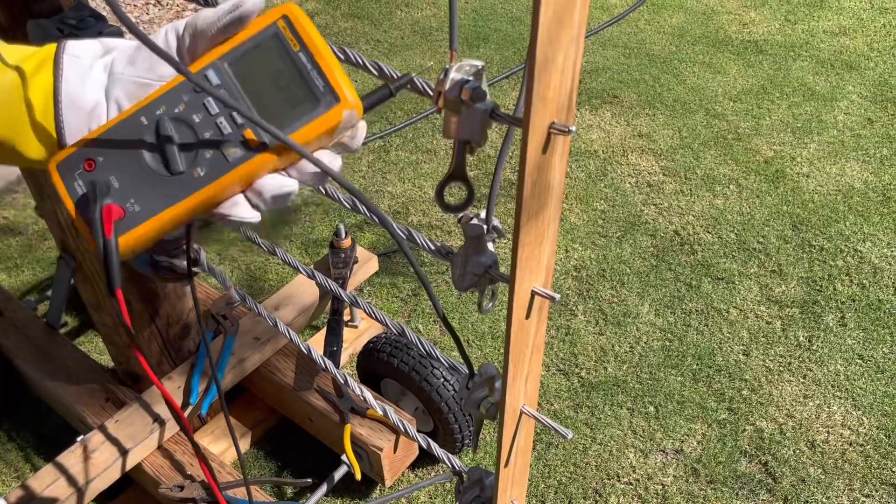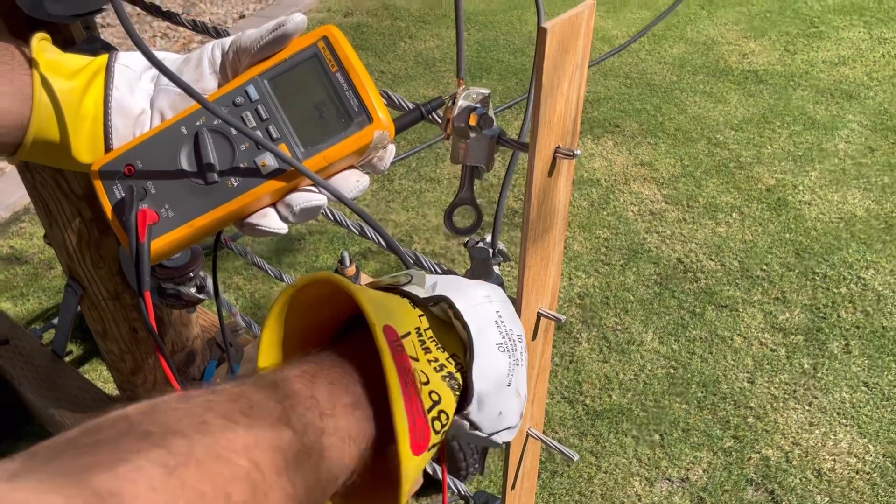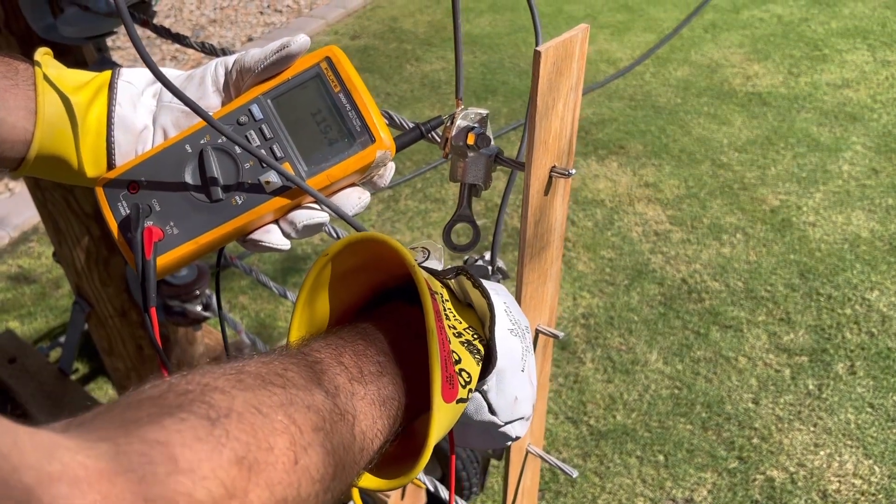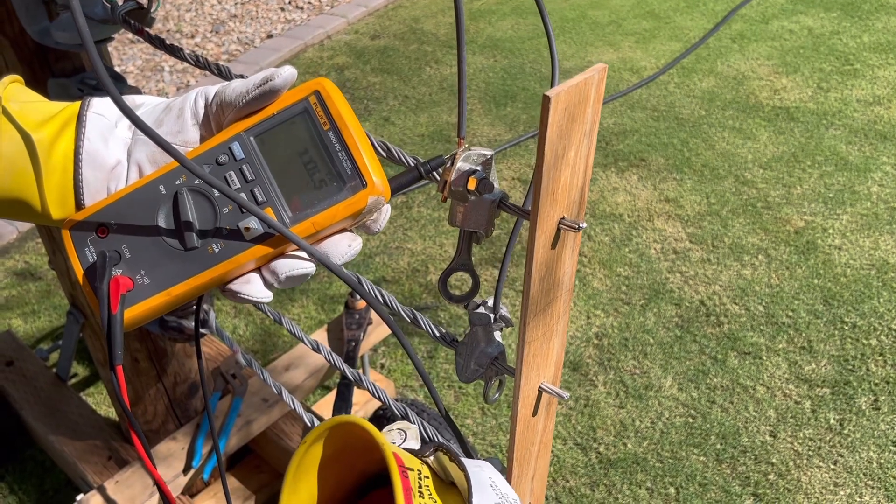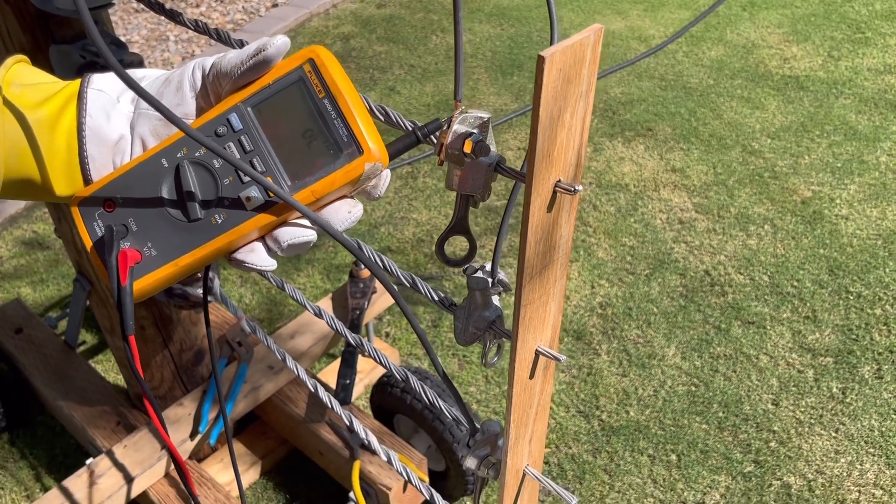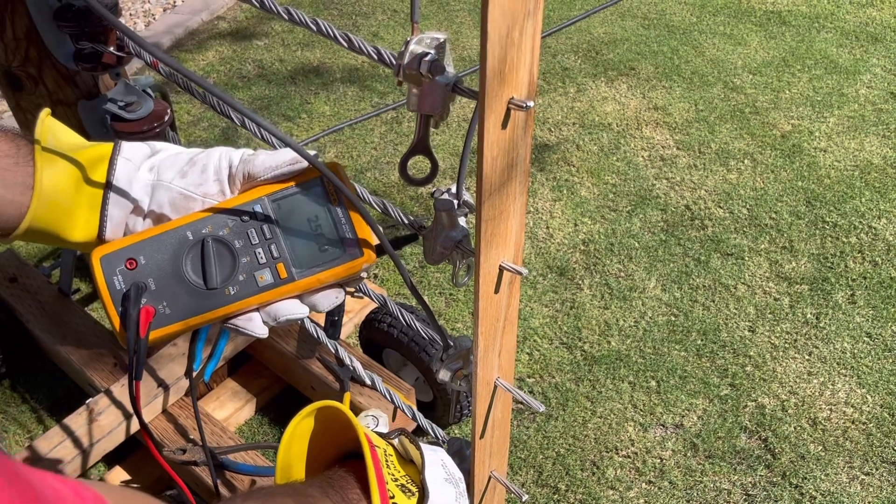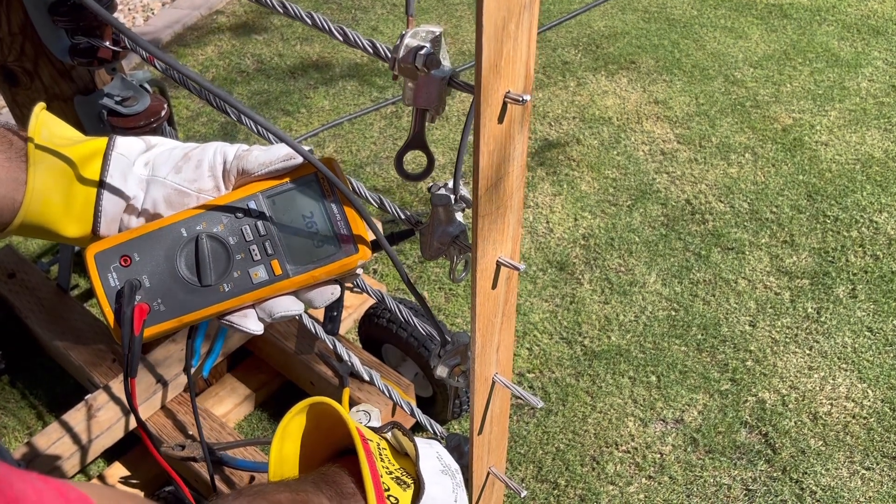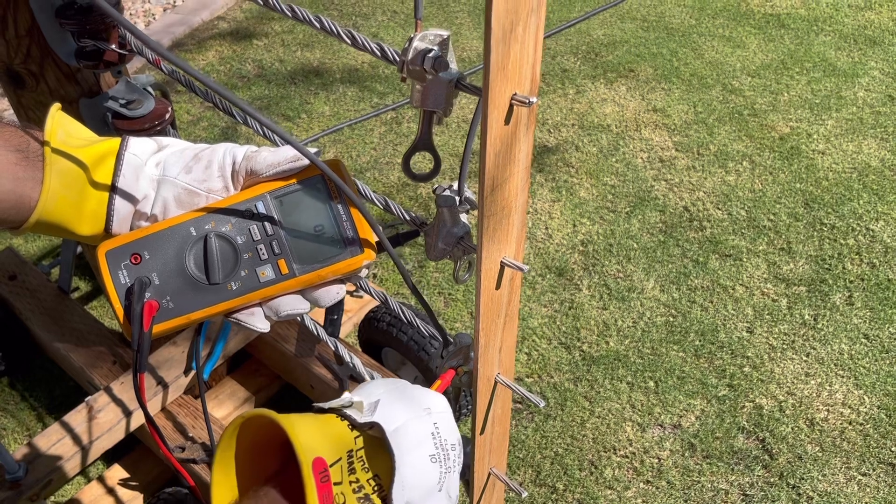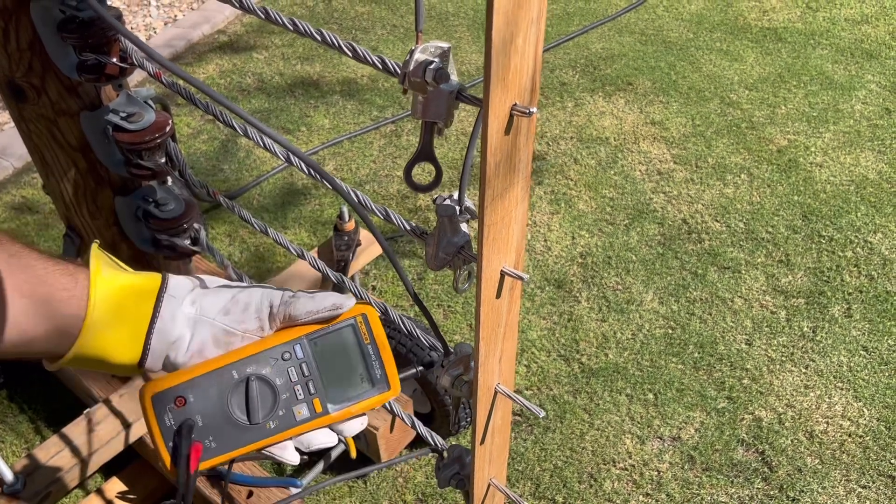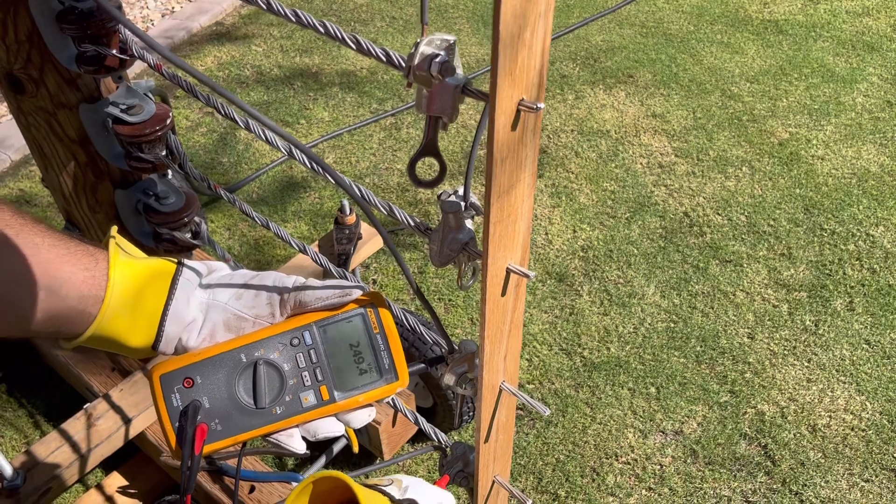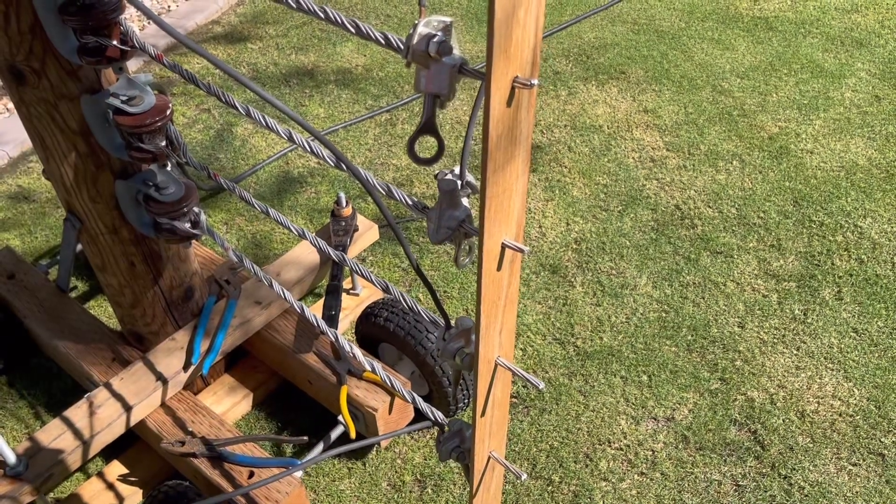And don't forget to always check voltage every time you operate those cutouts. We've got 119, 118, which would be my wild leg. 226, a little bit high, phase-to-phase. That one's 262, pretty high. 238, 249. Well, for the simulator, it's good voltage.